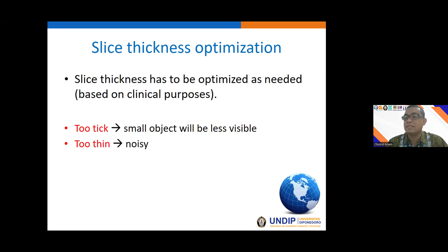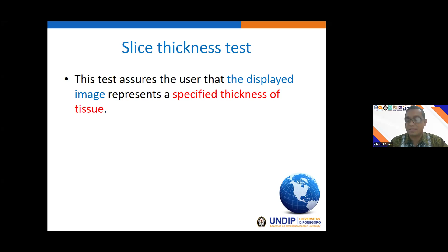The slice thickness is already shown and saved in the DICOM header. So we should test to ensure that the displayed slice thickness is similar to the specified slice thickness. The slice thickness should be measured in the routine quality control, and also in Indonesia in the compliance test.